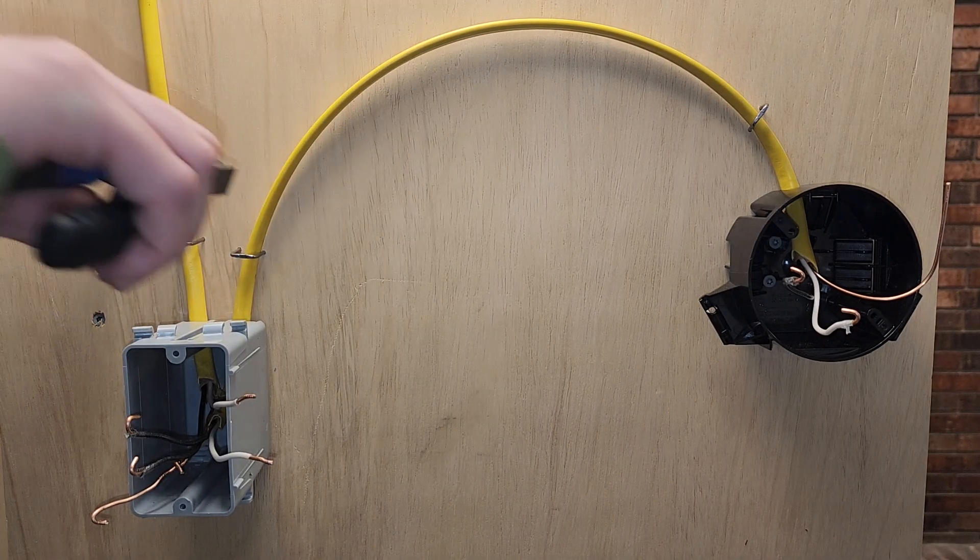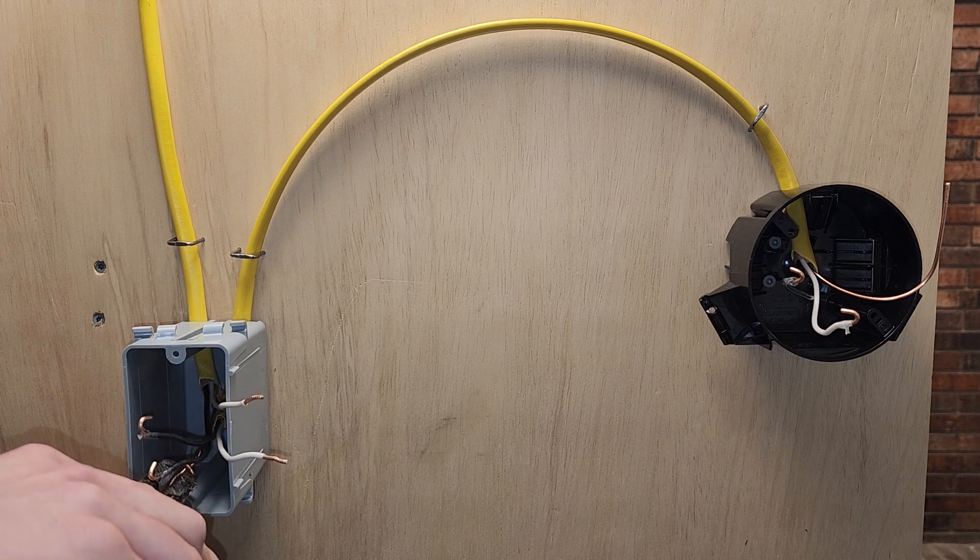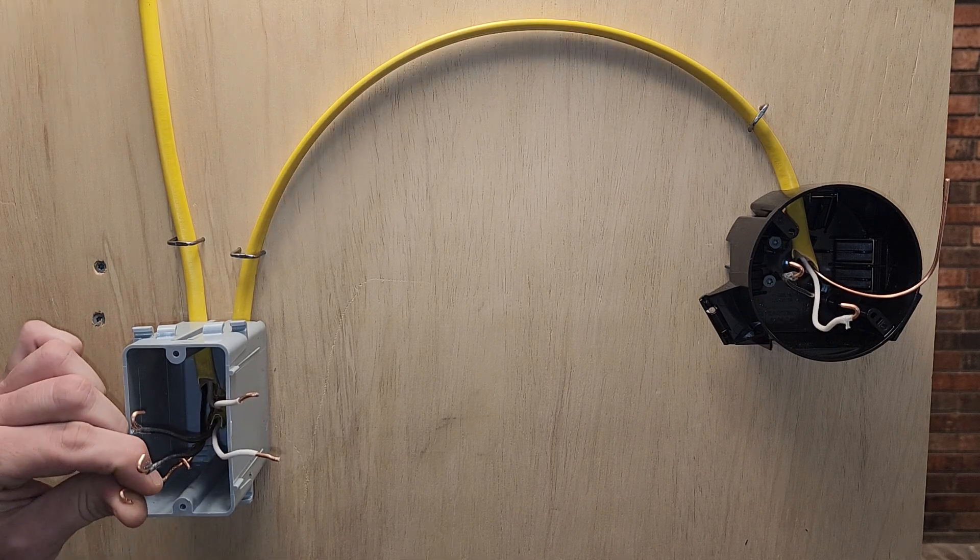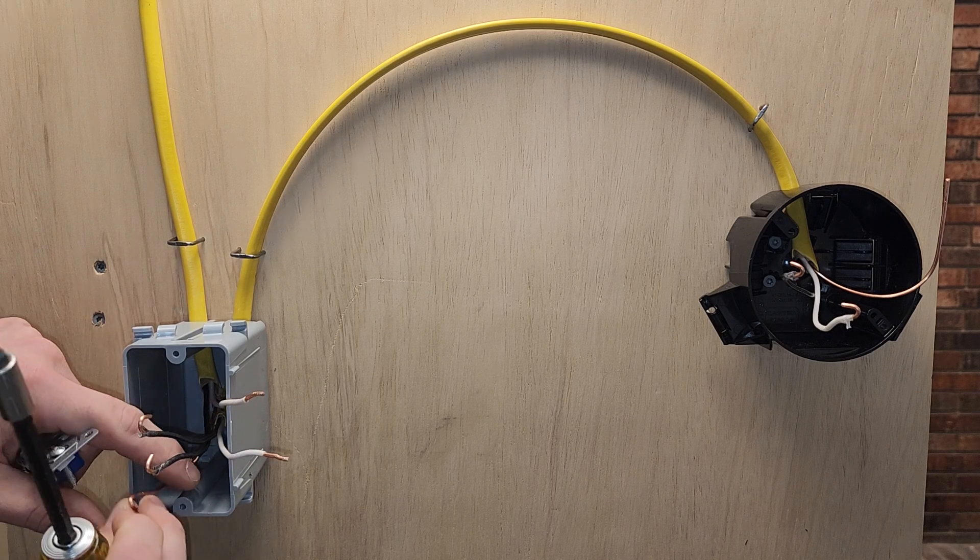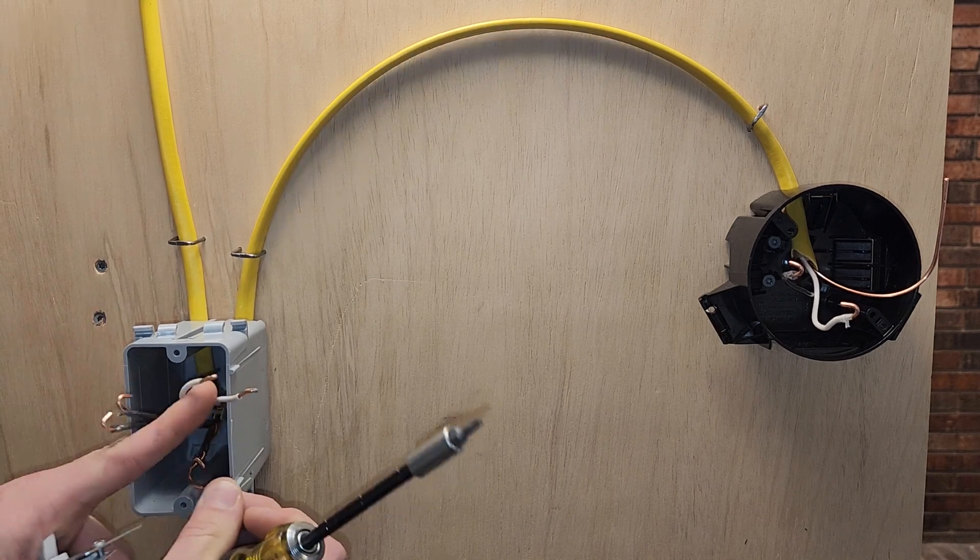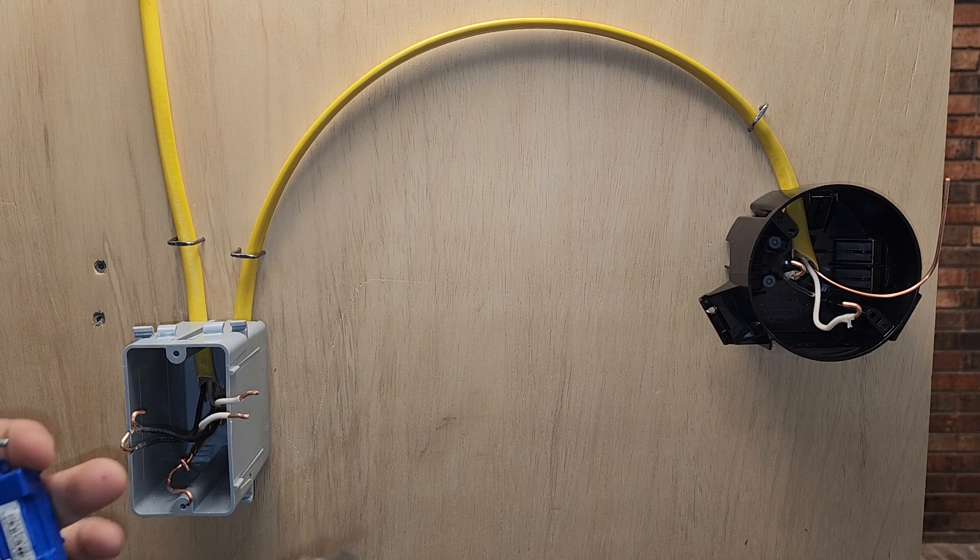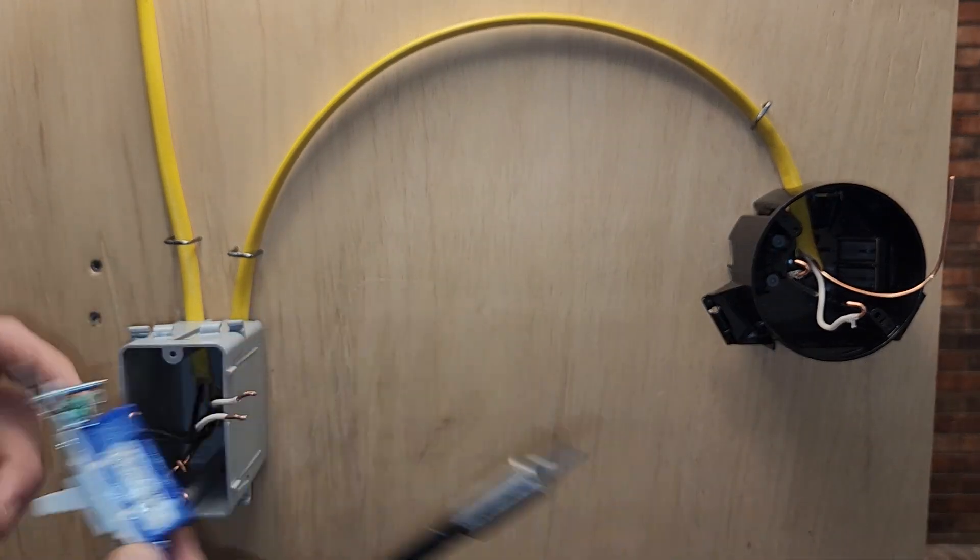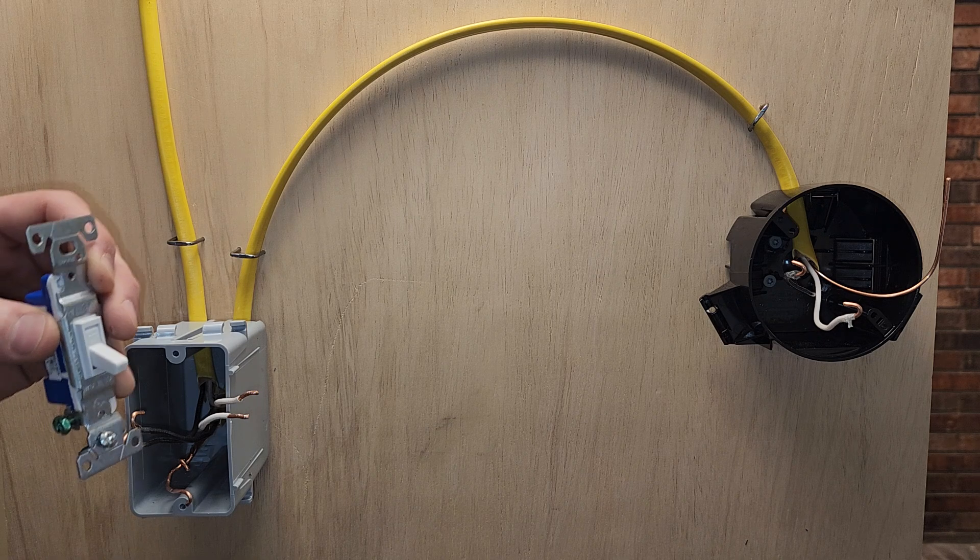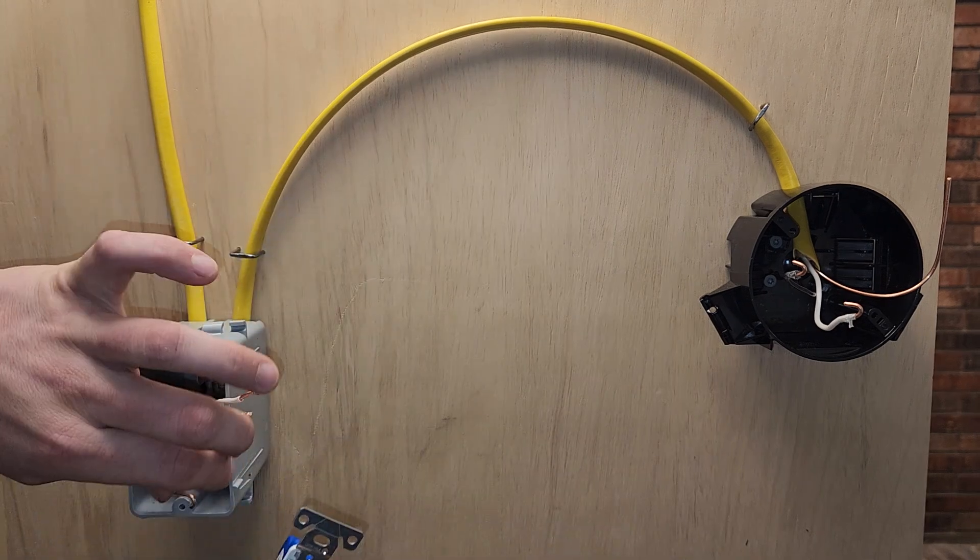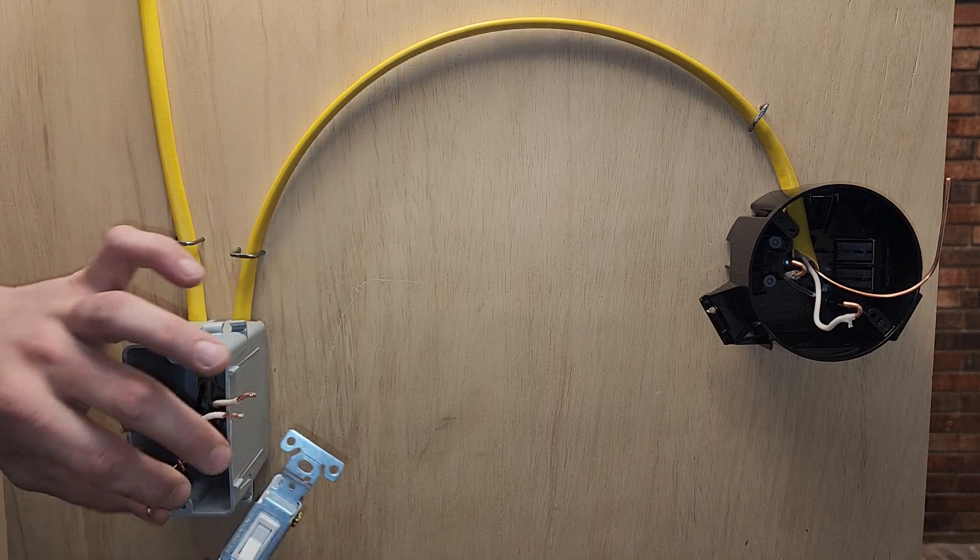I have our two grounds tied together already in this box with just the loops ready to be made up. An important thing to know is the loop that goes on to this green ground screw. You want to make sure the loop is going clockwise with the screw as it tightens for a good connection. If you have it the opposite way, you're actually loosening the connection.